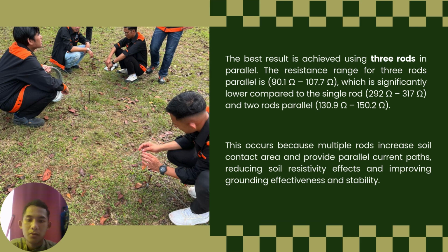This occurs because multiple rods increase soil contact area. When we put the rods, maybe around 3, 4, or 5, the cover area of the soil is increased. Every rod that we put in the soil will cover one zone, and if we multiply to 5 zones, it will increase the cover area. It will also provide parallel current paths, so the current will go through more smoothly. The current does not just go one way but three or two or more, depending on the rods.